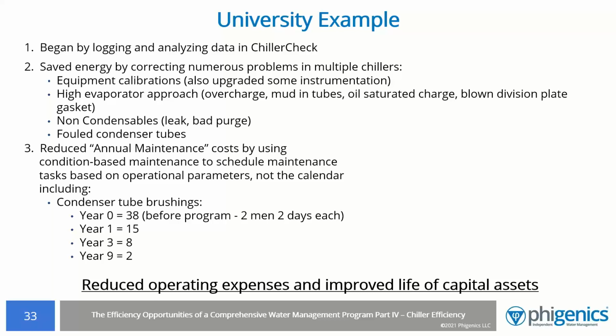So using condition-based maintenance, you can use it for leak testing, let's say. If your chillers' evaporator approaches are as good this year as they were last year, and your purge pump-out frequency is low, you don't need to shut that chiller down and leak test it. It's an expensive process. You can leak test based on evaporator approach rates.